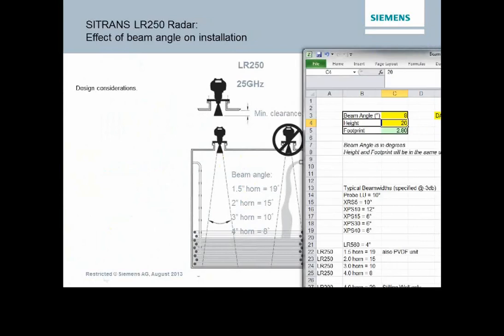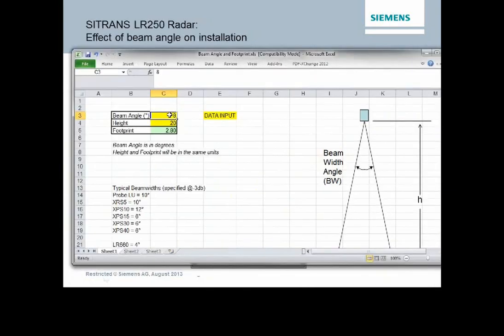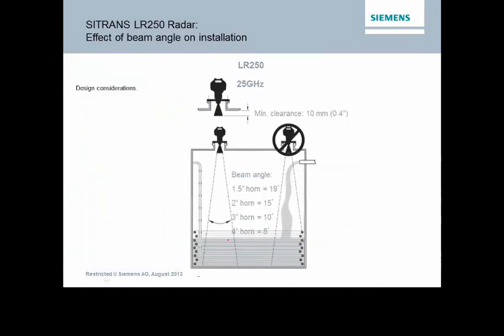We take a look at a beam angle. If I know I have a beam angle of 6 degrees, and the height of my tank is 20 feet, I know that my footprint is going to be 2 feet in size. So that gives me some ability, from a design consideration standpoint, to say, okay, I'm not going to put this unit 1 foot from the side of the tank because I know I'll be having some issues with that. So we can take a look at that up front in terms of beam angle and knowing what our footprint size is so that we can adjust accordingly.